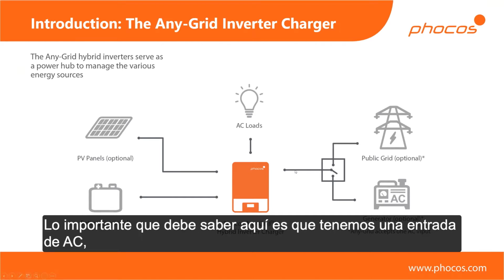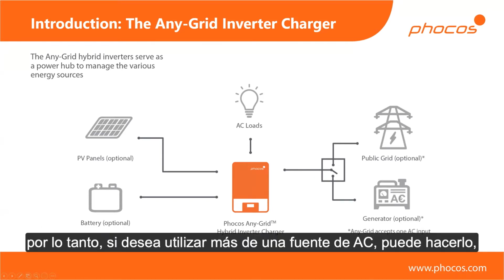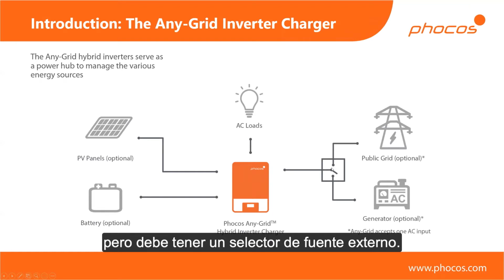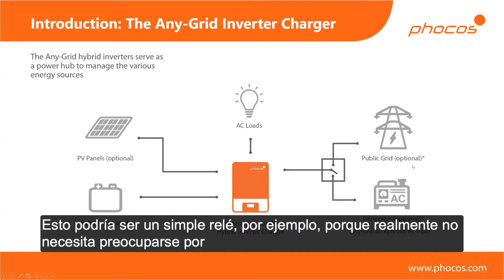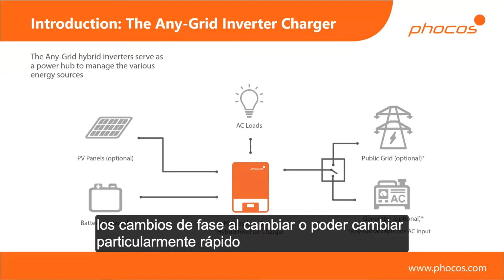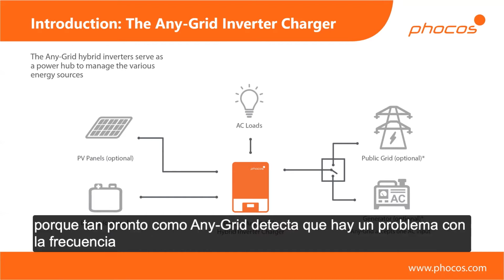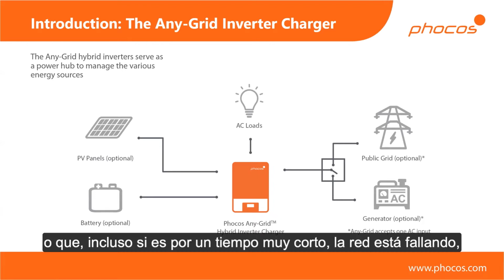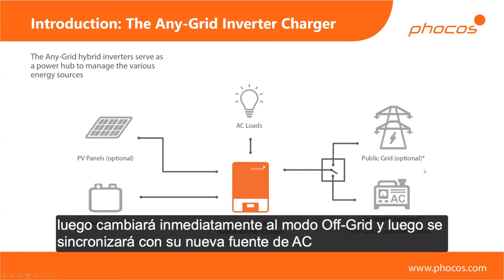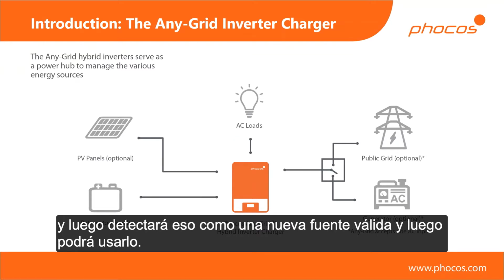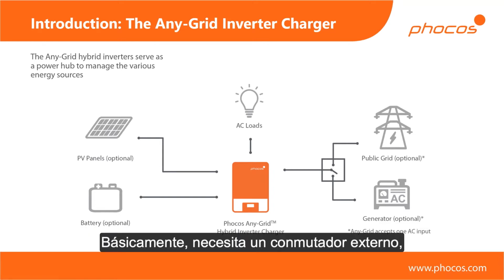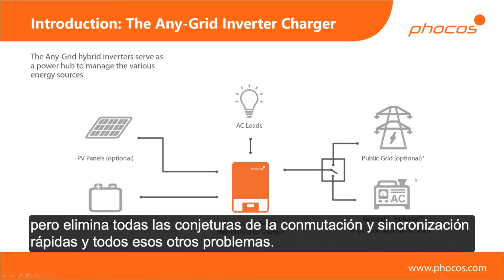What's important to know here is that we have one AC input. So if you do want to use more than one AC source, you can, but you need to have an external source selector. This could be a simple relay, for example, because you don't really need to care about phase shifts when switching over or being able to switch particularly quickly. As soon as the Any-Grid detects a problem with the frequency, or that the grid is failing even for a very short time, which is pretty much what will happen when you switch this over, it will immediately switch to off-grid mode, then resynchronize to your new AC source, detect that as a new valid source, and then use it. So you do need an external switch, but it takes all of the guesswork out of quick switching and synchronization and all of those other issues.